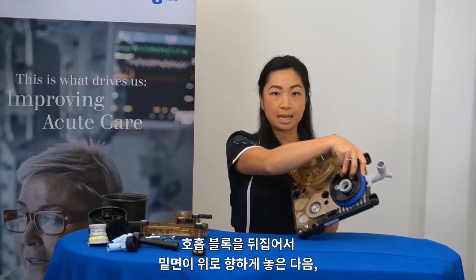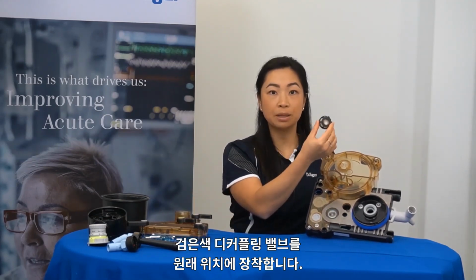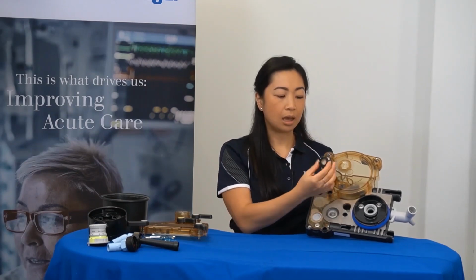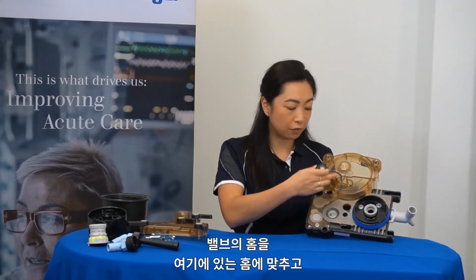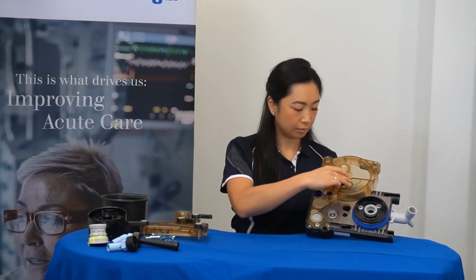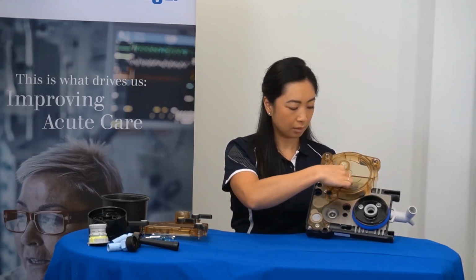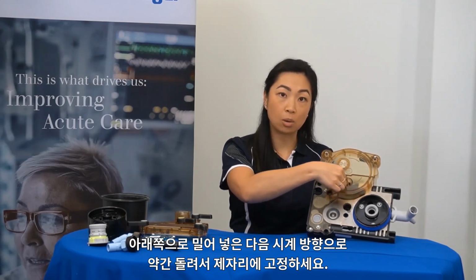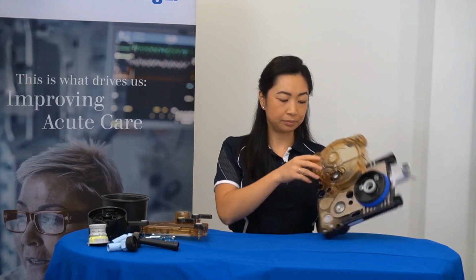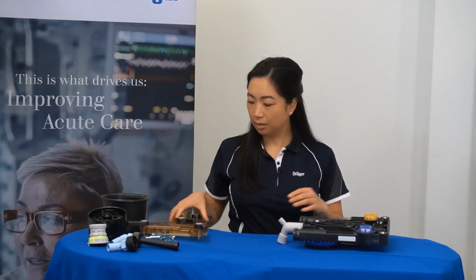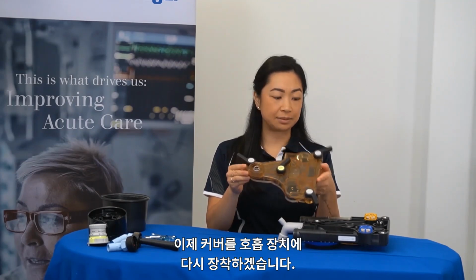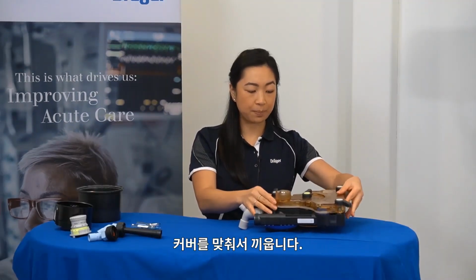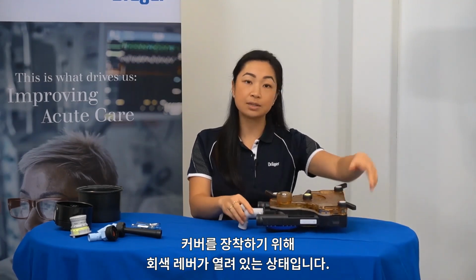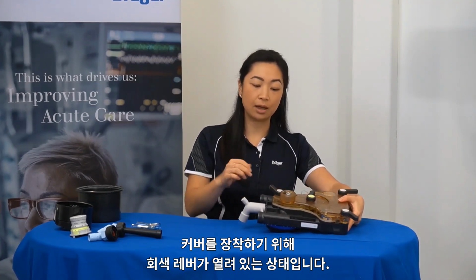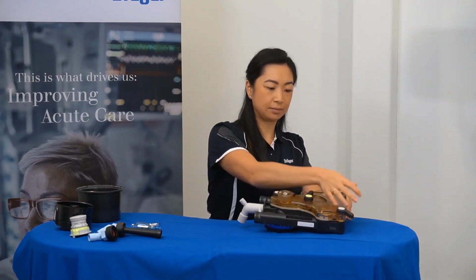By turning the breathing block around to the underside, you can then return the decoupling black valve to its position. Once again, aligning the notches of the valve to the notches here. Pushing down, and remember a slight clockwise turn to lock it into position. Now to return the cover to the breathing system. Align the cover up to its base. Ensure the grey levers remain open to allow you to attach the cover, and then close the levers.